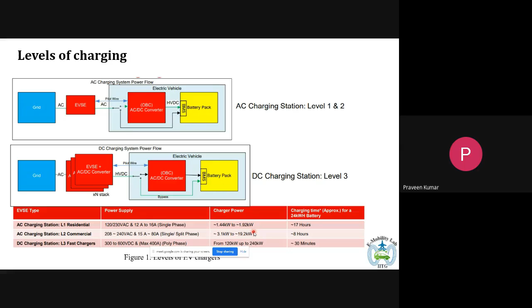If you install a level 2 charger at home, single phase is not the best choice. You will have to go for split phase or multi phase, a dedicated connection. That's the reality with large scale EV deployment. A normal domestic line won't support level 2 charging because it draws higher power, from 3 kilowatts up to 19 or 20 kilowatts. 20 kilowatts out of a socket isn't common in domestic situations today, but that will become a reality in the near future.